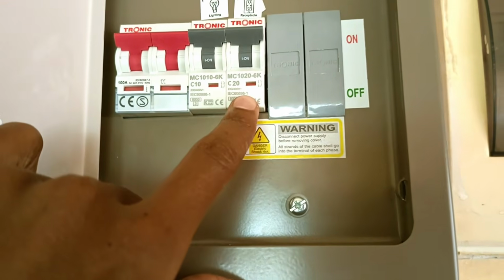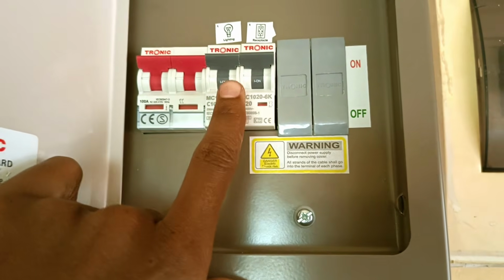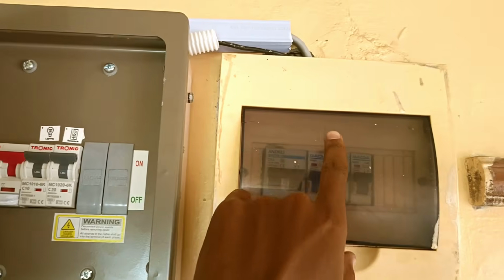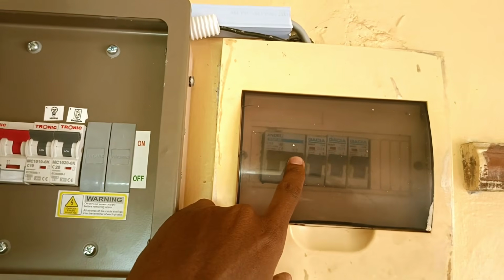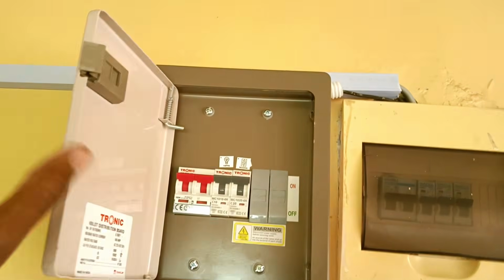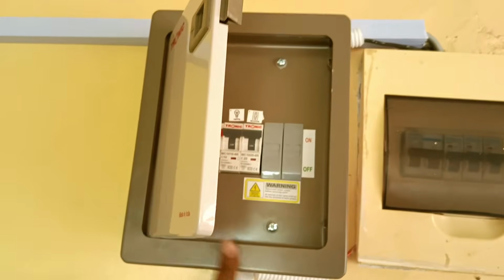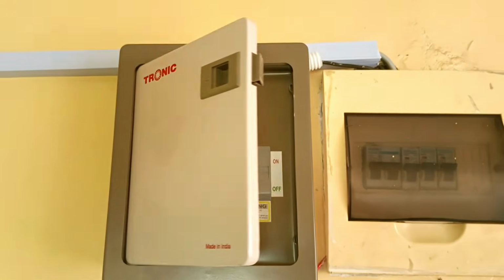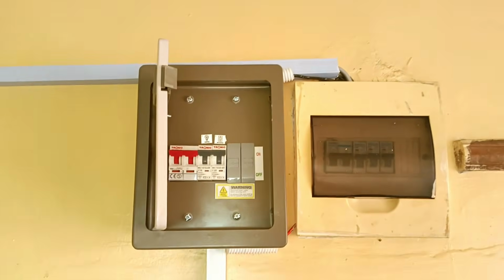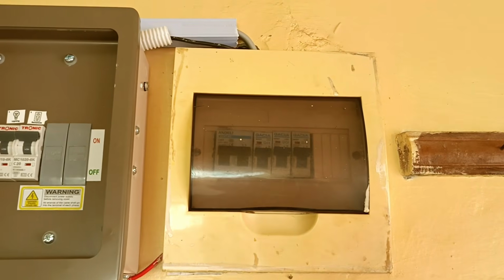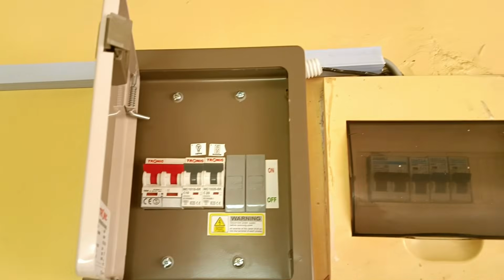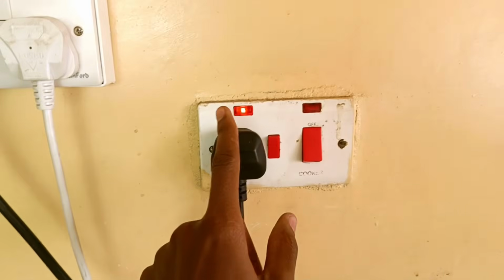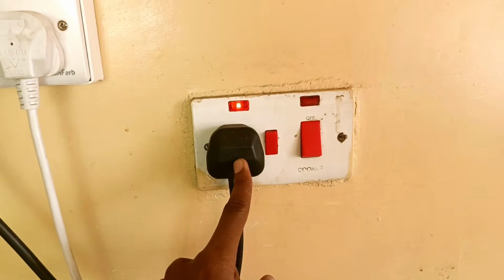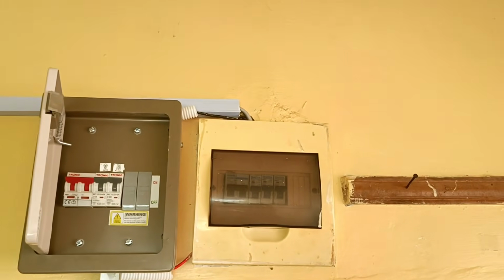as well as two circuit breakers, one for the socket outlets and one for the lights. So I have intercepted the power from here into the inverter and back here to power my backup loads. So with this setup, I do not even realize if the power is gone. The only circuits that I have not connected to my new backup load consumer unit are number 1, this cooker socket outlet, and number 2, the water heater in the shower.